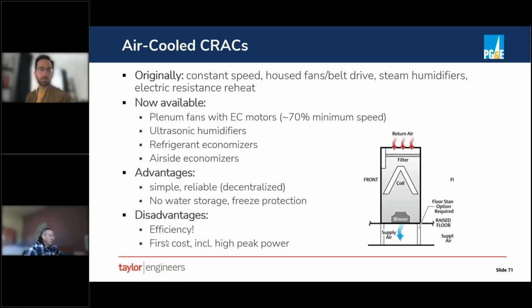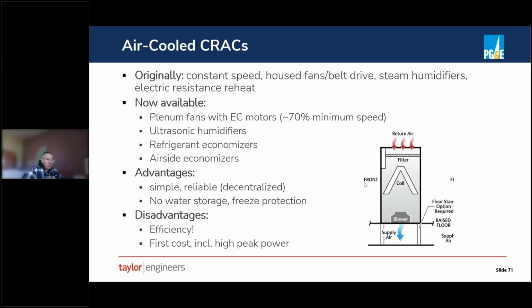And first cost. One of the big drivers of first cost in a data center is the peak power. If you're using something like an air-cooled DX system, it has a very high peak power because it has to be able to meet the load at the highest ambient temperature you're designing for. That means not only do you need to size the electrical service to the facility based on that, but you're typically also sizing your generator based on that. If you've got a peak PUE of 1.5, for example, that means you need 50% more generator capacity than just the capacity needed by your computer.